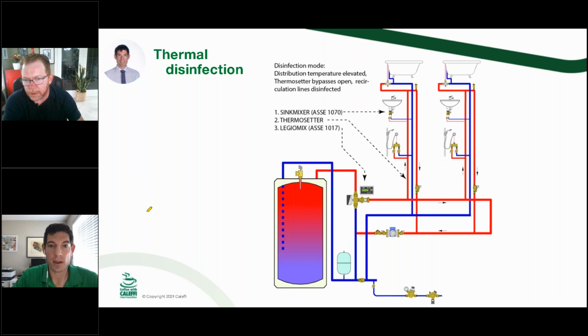So on the next slide, the difference here is we are now in disinfection mode. So let's say we're supplying 160 degrees coming out of the mixing valve. Let's say there's a lot of heat loss and it's coming back at 140. We keep that for half an hour. We've disinfected the lines that were up to temperature there. However, water is lazy, so it's going to take that path of least resistance up that first riser. We haven't really guaranteed that we've sent that warm water all the way out to the riser on the right.